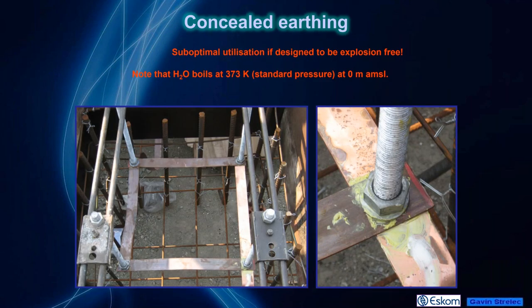We know that if we want to avoid having an explosion in concrete, literally by forming steam, we need to design very conservatively so that the allowable temperature rise is maybe only 50 degrees. So we are putting in massive conductors in order to limit temperature rises and to avoid damage to the concrete.